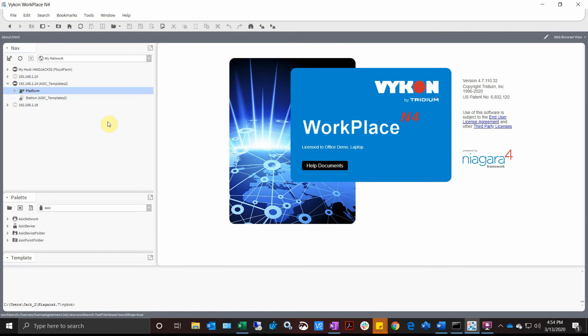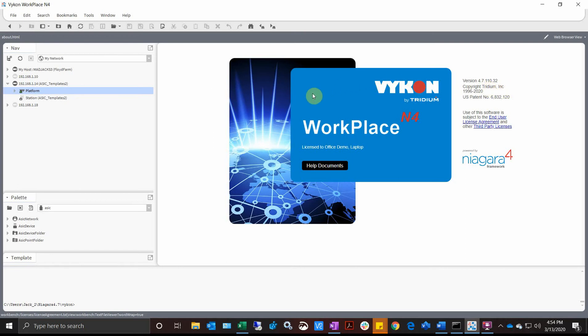That's the easiest way. Once you upgrade to a new version of software like 4.7.110, you should either keep 4.6 on your machine or multiple versions. You can run different instances of workbench on your machine for different job sites, or the best way is just to keep the SMAs up to date and keep the JACEs up to date.